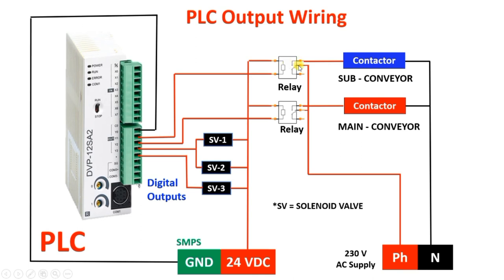The NO terminal of the first relay connects to one terminal of the sub conveyor contactor, and the NO terminal of the second relay connects to one terminal of the main conveyor contactor. The other terminal of both contactors connects to neutral. If a relay is on, its common and NO will close, giving supply to the contactor, which energizes and turns on the respective conveyor motor.